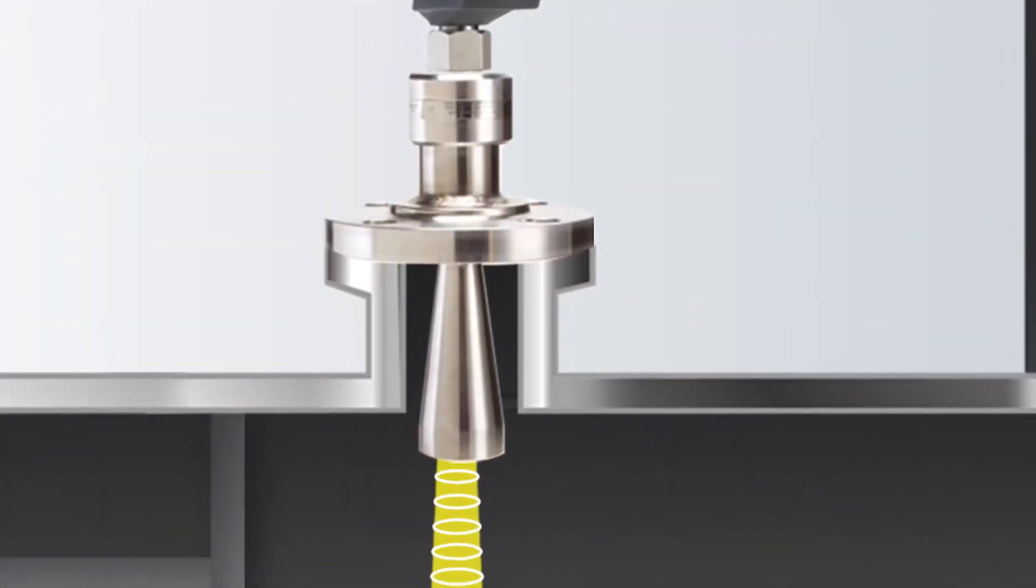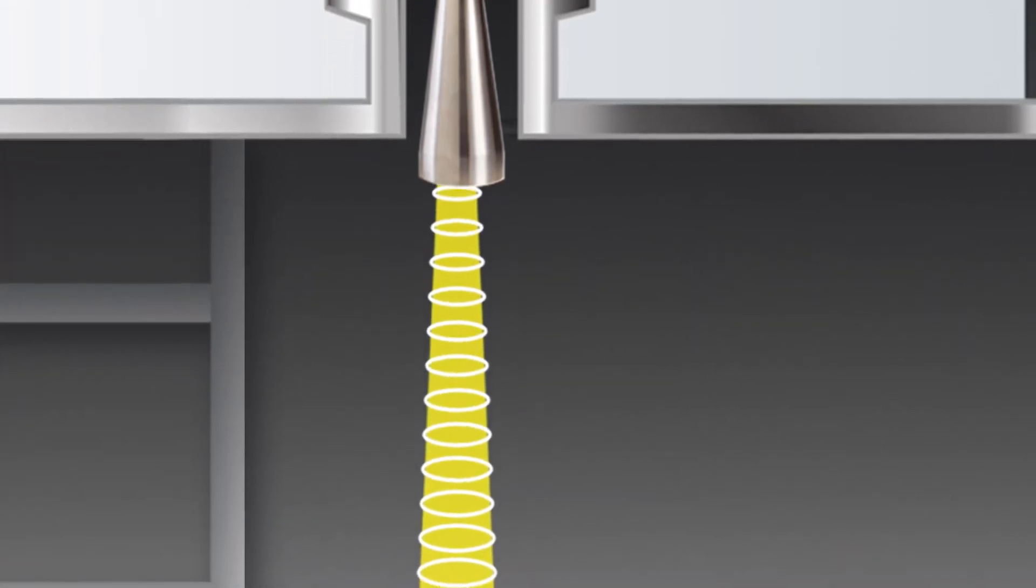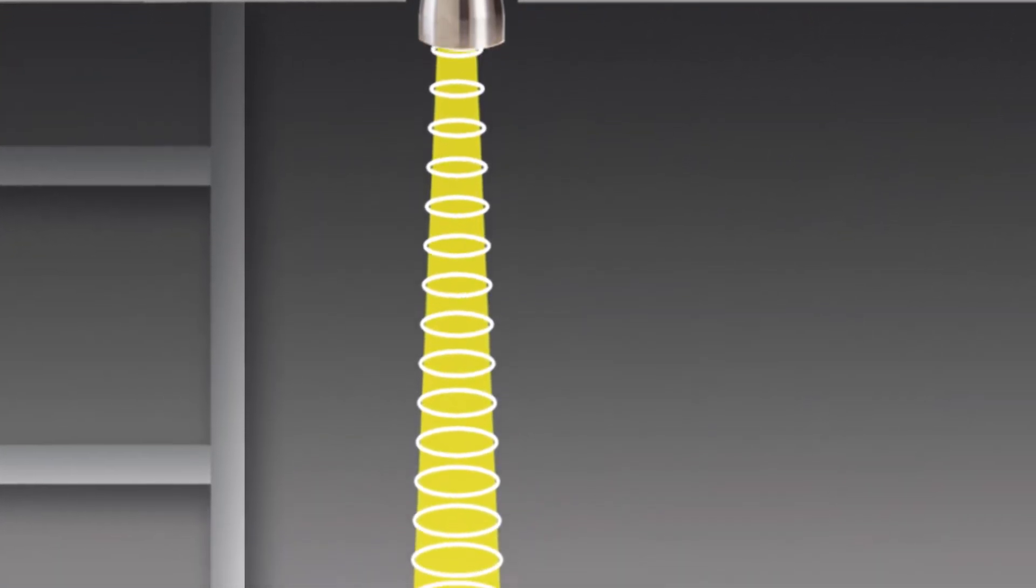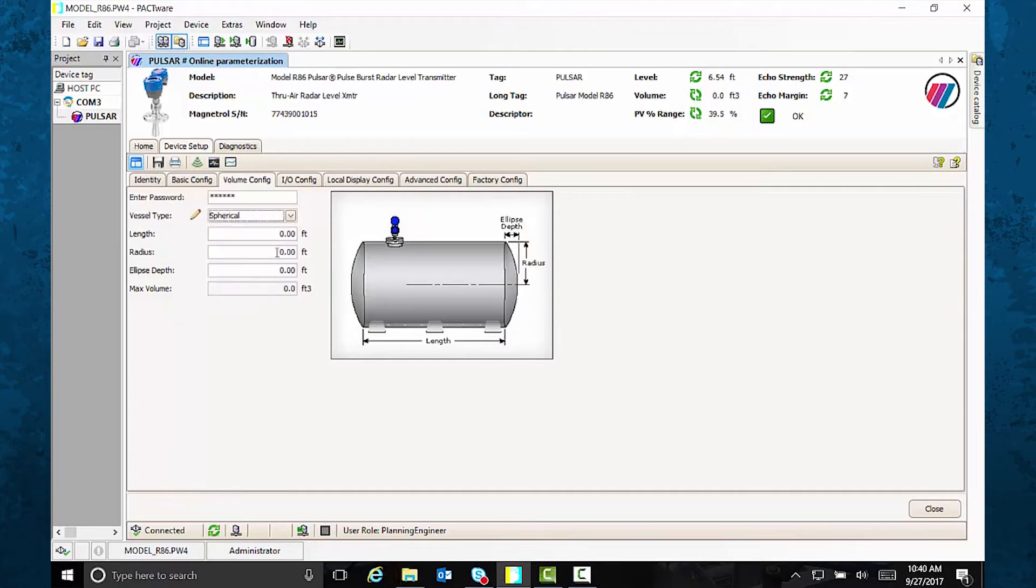The Pulsar Model R86 has a 26-gigahertz radar signal with a shorter wavelength that offers smaller antennas, a narrower beam, and improved accuracy. You can also set it up for your precise need using volumetric configuration. It has nine common tank shapes and a strapping table for uncommonly shaped vessels.